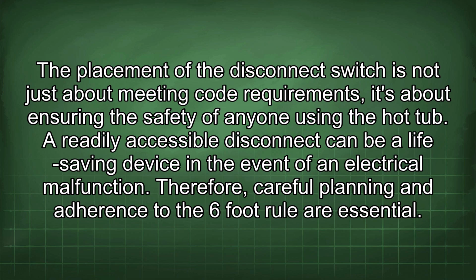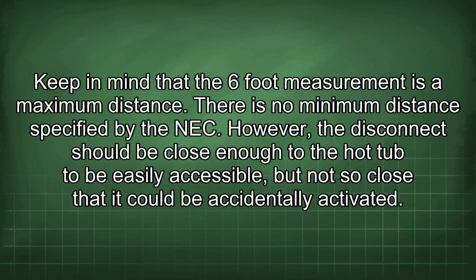A readily accessible disconnect can be a life-saving device in the event of an electrical malfunction. Therefore, careful planning and adherence to the 6-foot rule are essential. Keep in mind that the 6-foot measurement is a maximum distance. There is no minimum distance specified by the NEC. However, the disconnect should be close enough to the hot tub to be easily accessible, but not so close that it could be accidentally activated.